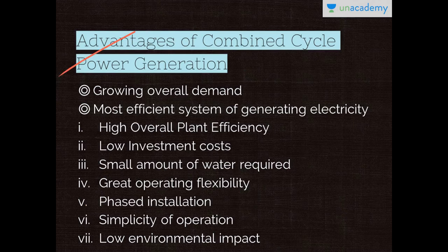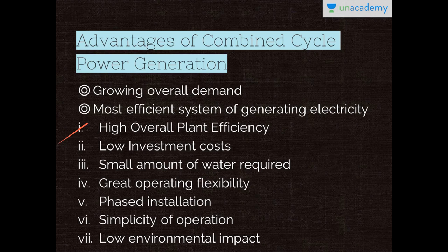Moving on to the advantages of combined cycle power generation. The worldwide demand for combined cycle power plants is growing dramatically, with some experts forecasting explosive growth over the next decade. The high overall plant efficiency — efficiencies exceeding 50% can be attained. Low investment costs: two-thirds of the output is produced in a gas turbine and only one-third in a steam turbine, so investment costs are approximately 30% less than for a conventional steam power plant. Small amount of water required: the cooling water required is only about 40 to 50% as much as for a steam plant.